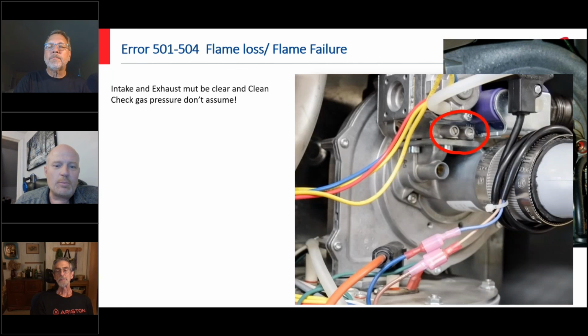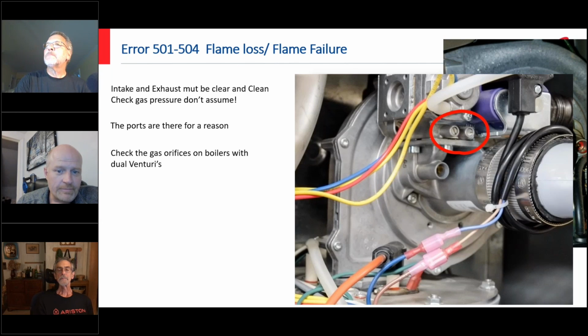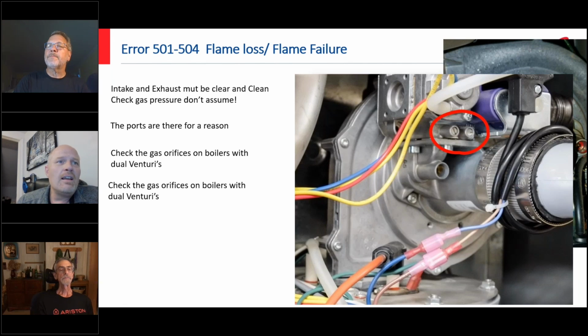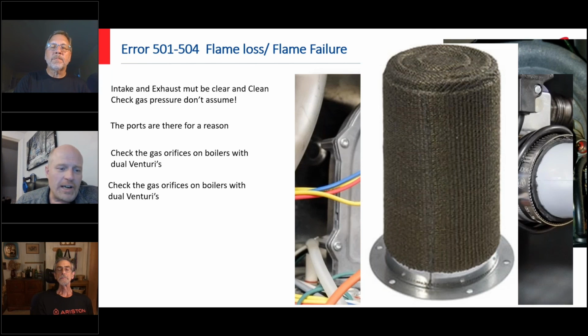Okay, we've got two little test ports for testing your gas pressure. They are there for a reason. It's because we do want you to check it every time you do a combustion test, and especially when troubleshooting. Check the gas orifices for any boilers with dual Venturis. And don't be afraid to take apart the burner. Take this piece to the kitchen sink, wash it. They do get plugged up over time.